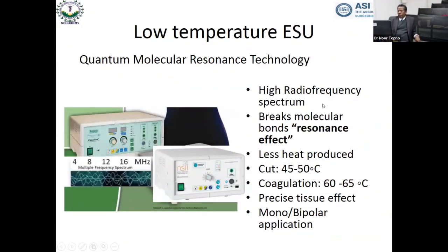This is something that is new. It's basically a high frequency radio frequency that is used here. And here actually, unlike the electrosurgical unit, it is not the heating that is important, but the resonating effect. Just like when soldiers march over bridges, they are instructed to break their march, because if their frequency matches the resonating frequency, the bridges are likely to collapse. It is this resonance which breaks the bonds between the tissue, and that leads to a cutting effect. The heat produced is somewhere around 45 to 65 only, and it has both monopolar and bipolar action, and the tissue effect is very, very precise.